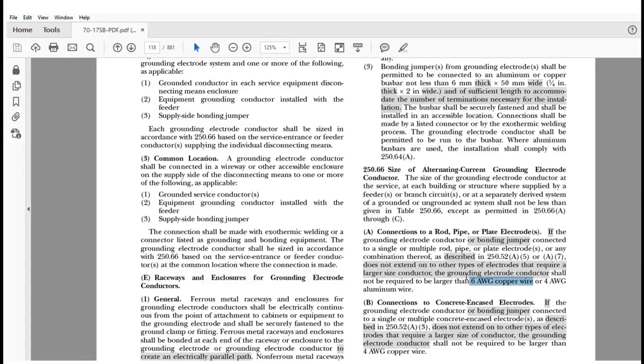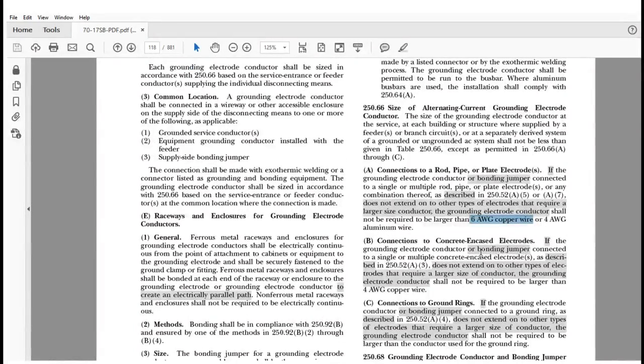Now, the significant importance of this, and this applies to all of them because I want to talk about them all in general, is that even for the concrete encased electrode, the same revision took place. They removed the sole connection. It's the same aspect where you're connecting one or multiple concrete encased electrodes together. That doesn't have to be larger than a 4 AWG copper. It doesn't give any provision here for aluminum, but it's 4 AWG copper.